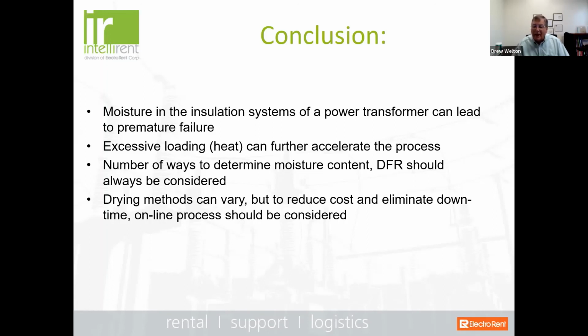Now, keep in mind that ultimately you can take an oil sample while the transformer is online, but it's certainly not recommended. And the reason it's not recommended is the catastrophic event of having a winding failure or something internal to the transformer happen while you're taking that sample can be very, very dangerous. So it's not recommended. So time of year is really relative to when it's applicable to be able to take your transformer offline. Okay, just a couple more questions.